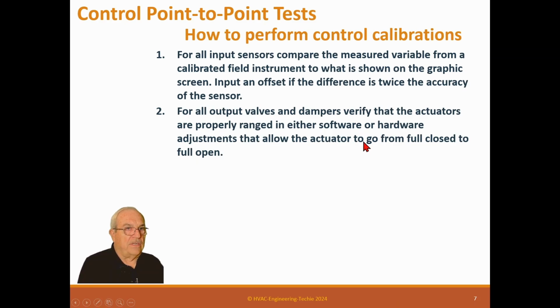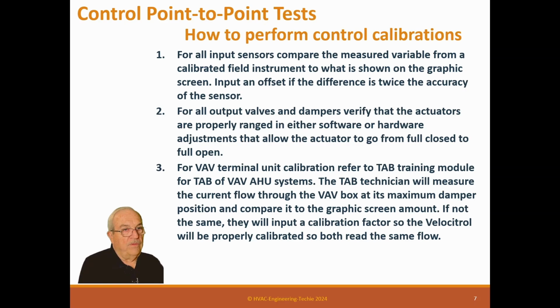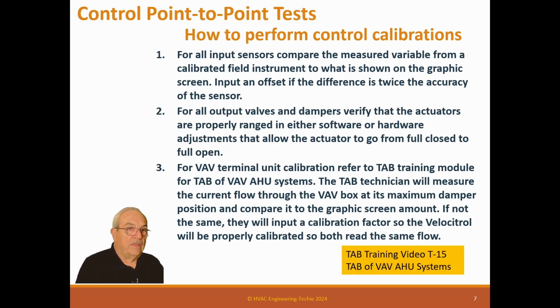For all output valves and dampers, verify that the actuators are properly ranged, in either software or hardware adjustments, to allow the actuator to go from full close to full open. For VAV terminal unit calibrations, refer to TAB training modules for TAB on VAV air handler systems. The TAB technician will measure the current flow through the VAV box at its maximum damper position and compare it to the graphic screen amount. If not the same, they will input a calibration factor so the Velocitrol will be properly calibrated so both read the same flow. That's important. And of course, our TAB training T15 shows how to actually do that.